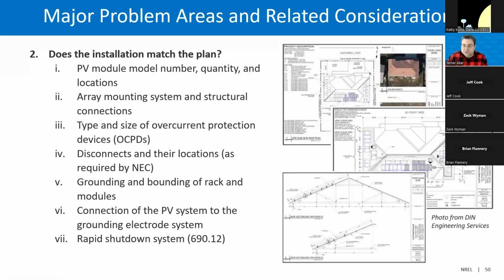So continuing with the major considerations, the second thing to check is, does the installation match the plan? Another major problem area is correspondence to the plan, and the inspector should verify whether the PV module model number, quantity, and locations, array mounting system and structural connections, type and size of the overcurrent protection device, disconnects and their locations, grounding, bonding of rack and modules, connection of PV system to the grounding electrode system, and also the rapid shutdown system match the plan or not.